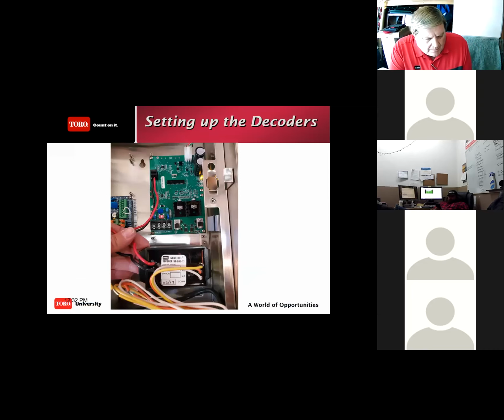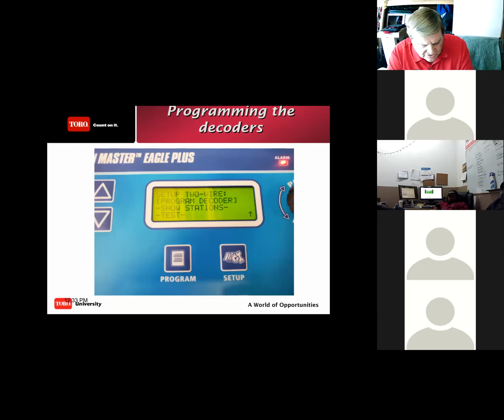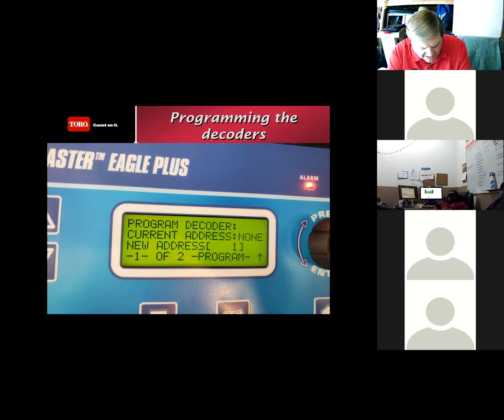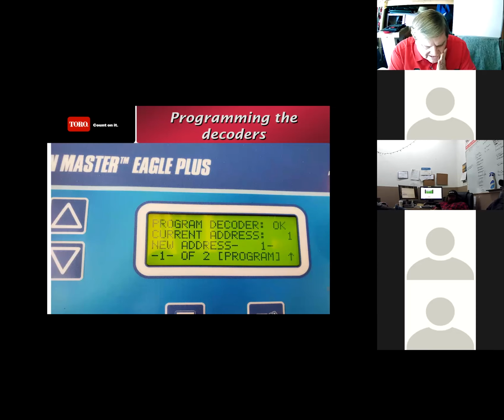So make certain you have the brand specific decoder with the brand specific controller. You hook it up to the programming port as you see here and as you saw earlier in the screens. You connect it up, all right? Set up the 2-wire decoder, program the decoder. All right, I'm going to address it right now. I'm going to call it station number 1. I click to address it. It says, okay, I communicated. Guys, the decoders have 2-way communication. So now it says it's okay. Address is now considered station 1.